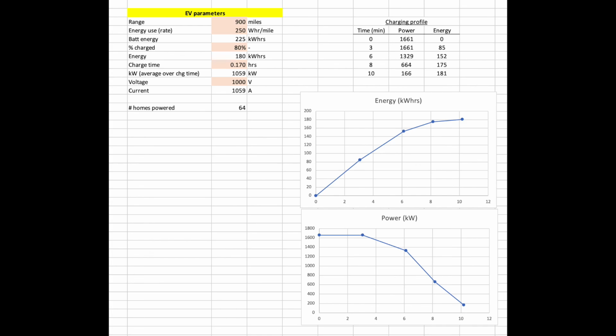So the average power is, as I said, 1 megawatt, translating to 1 kiloamp average. But if you look at the charging profile, you'd need much higher power delivered in the beginning, for the first 4 to 6 minutes or so, before it starts to taper off. That power requirement would be 60% higher, as you can see from this graph, meaning at the same voltage, 1.6 kiloamps.